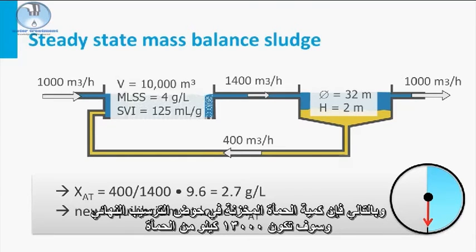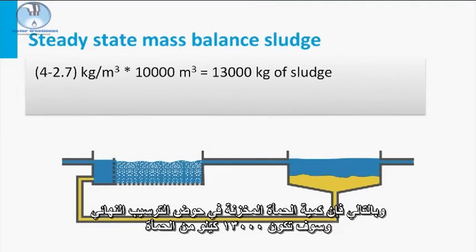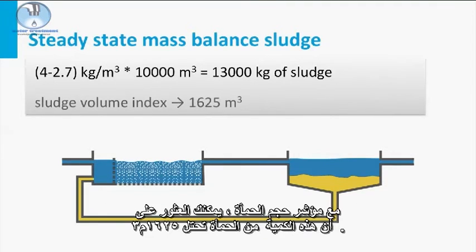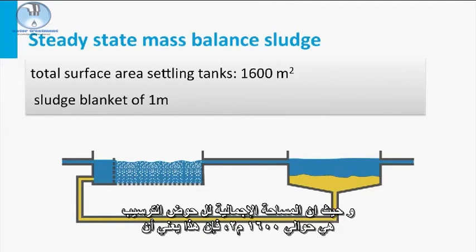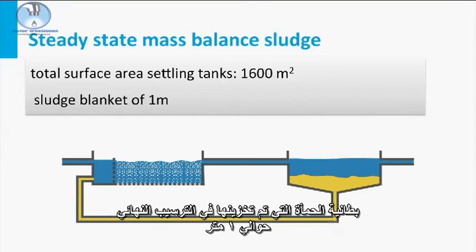So the amount of sludge stored in the final clarifier will be 13,000 kilograms of sludge. With the sludge volume index you can find that this amount of sludge will take 1625 cubic meters. Since the total surface area of the two settling tanks is around 1600 square meters, this would mean that the sludge blanket that is stored in the final clarifier is approximately 1 meter.